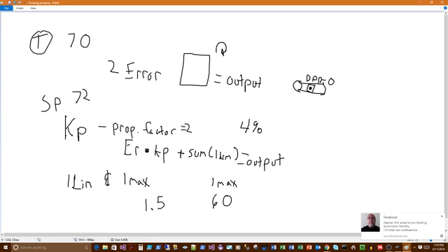And then what happens is this error right here, which we know comes from the difference between set point and temperature, that error plus or times the proportional factor plus the sum of your ILim, which we know is 1.5, and that gets 1.5 plus 1.5 plus 1.5 each time it cycles, as long as it doesn't go greater than Imax, equals output. So essentially, we could get to the point where we get 64%.